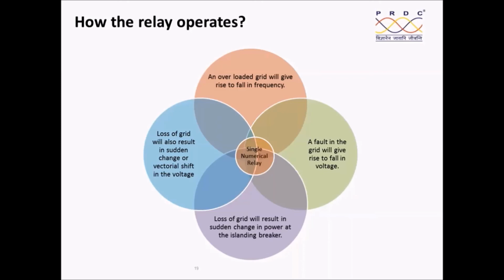Loss of grid will result in a sudden change in the power at the islanding breaker. Therefore, a voltage vector shift can happen, or there is a sudden variation in the power. You can try to quantify the jump in the power, that is, the magnitude change, and by that also you can find out that there is some problem, and you can also get islanded. Loss of grid also results in a sudden vectorial shift in the voltage. Based upon these things, we will be able to ensure that proper islanding happens.